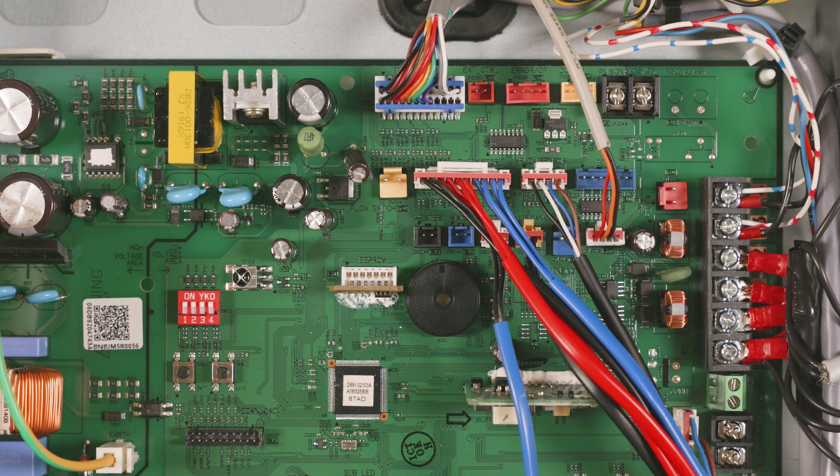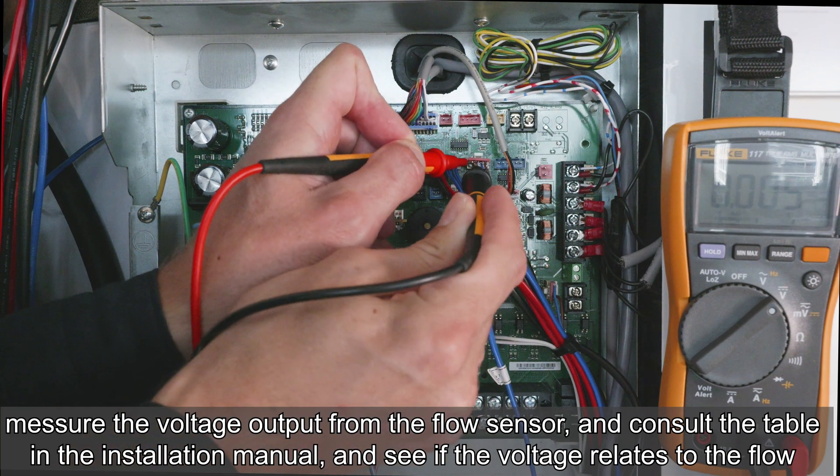First reconnect the sensor before going to the next step. The next step is to measure the voltage output coming from the flow sensor. Measure the voltage output from the flow sensor and consult the table in the installation manual to see if the voltage relates to the flow.